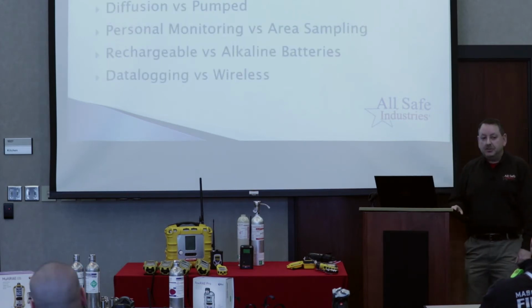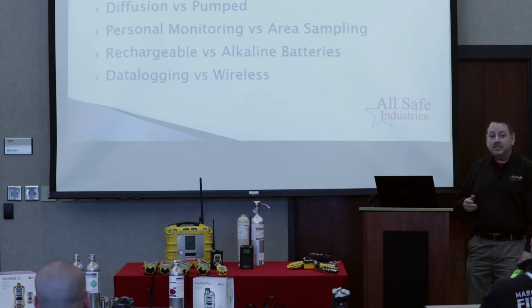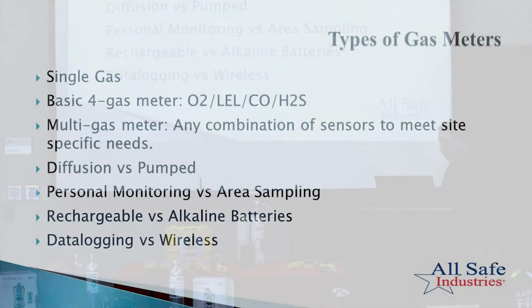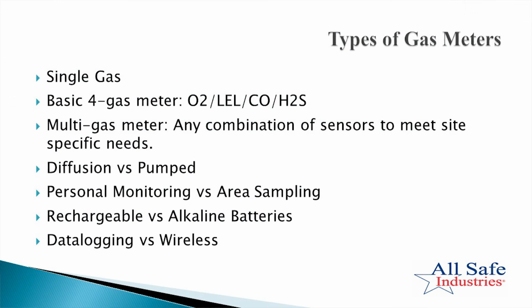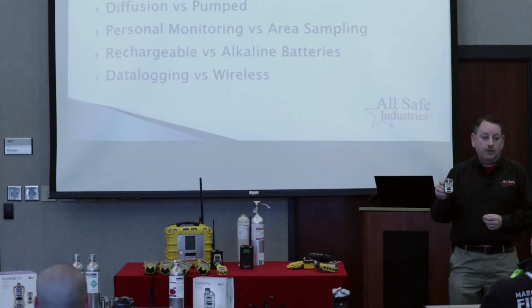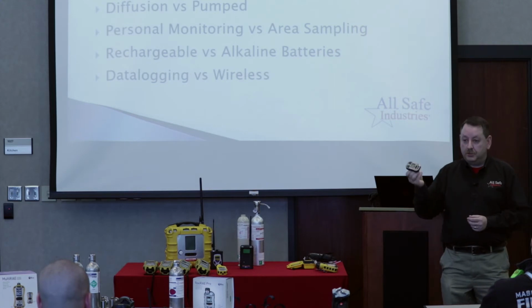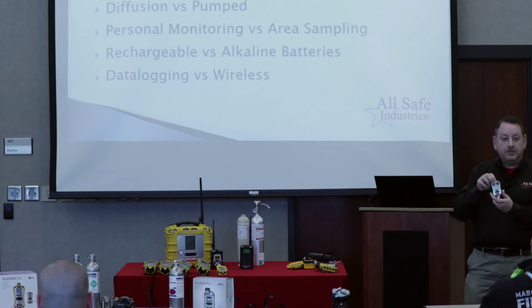So the next thing I like to do is just go over the different types of gas detection instruments available, and I'm going to grab a few and I'll start passing them around the room. So the first type of instruments I'll just inform you about are the single gas instruments, okay? So I'm holding the ToxiRAE 3. This is a real simple single gas instrument, very inexpensive, really a throwaway instrument. It's only available for CO and H2S, but that's what a little single gas meter looks like.